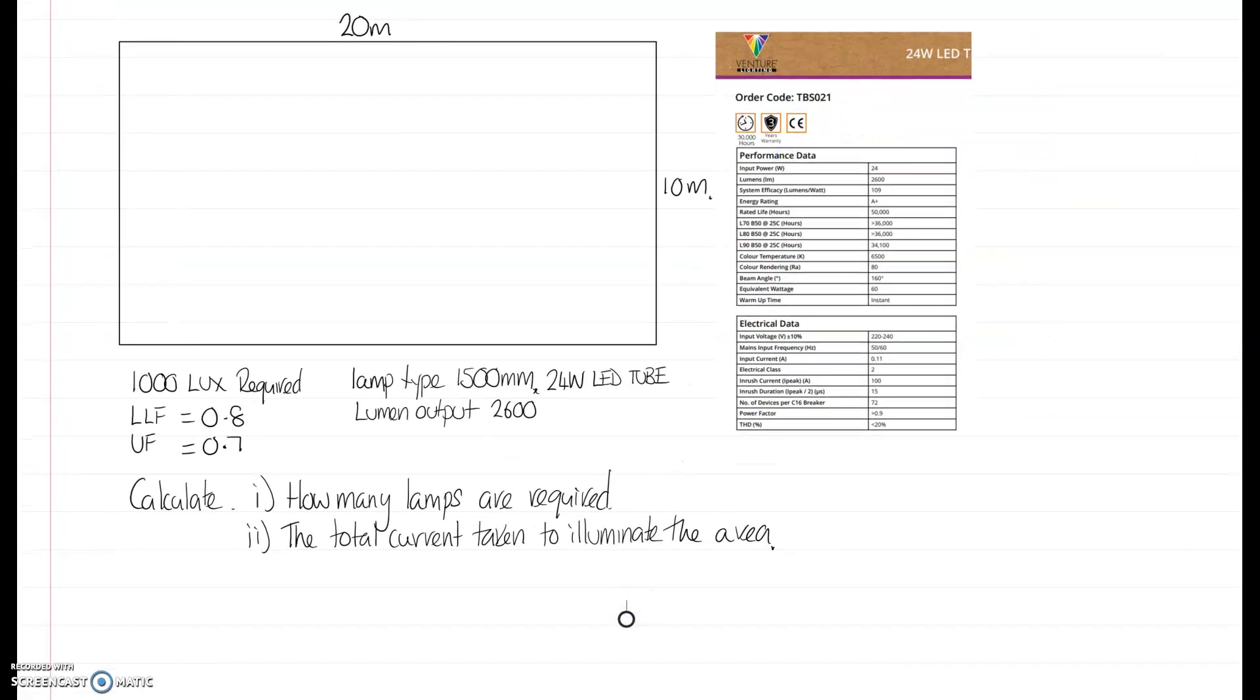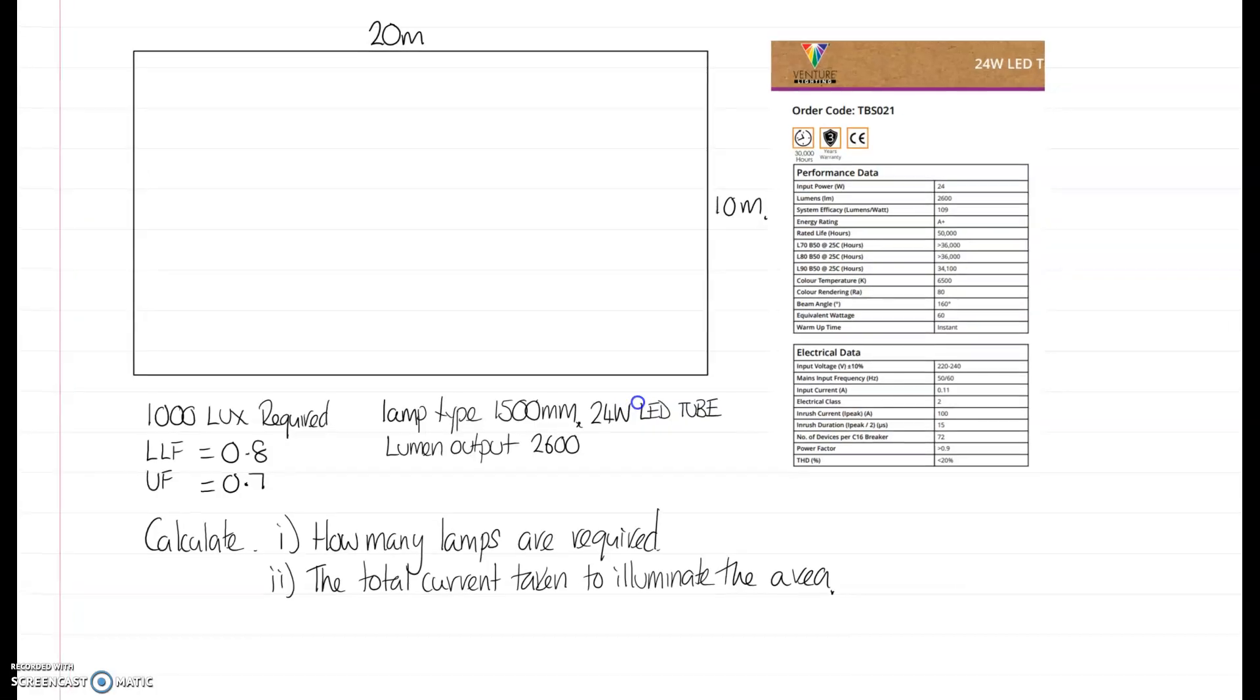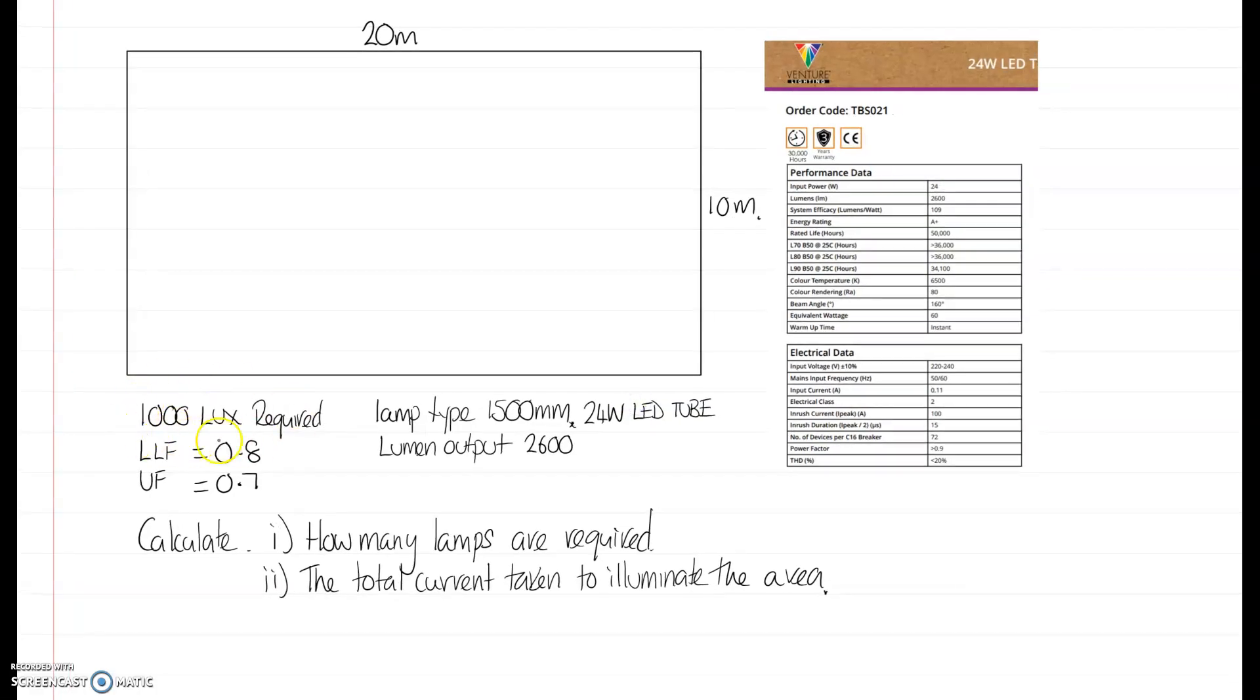First thing we need to do is work out how many lamps are required, and we're going to work out the total current taken to illuminate the area. So the data: we need 1,000 lux in this area, light loss factor is 0.8, that is a little bit steep but I'm setting it at 0.8 anyway, and the utilisation factor is 0.7. First thing we do is write our formula down and do the maths.